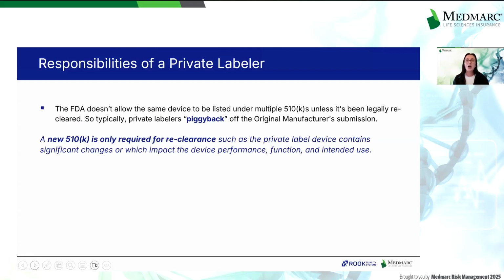The FDA does not allow the same device to be listed under multiple 510(k)s unless it's been legally re-cleared. So typically, private labelers will piggyback off the original manufacturer's submission. However, a new 510(k) is only required for re-clearance, such as if the private label's device contains a significant change from the original device, which impacts the device's performance, function, and intended use.